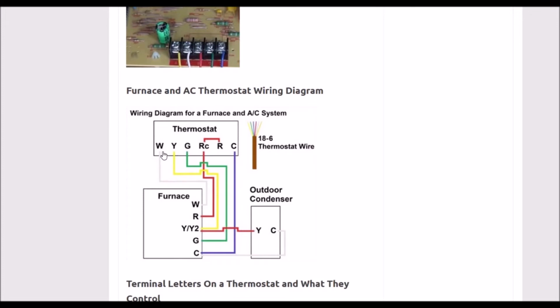And this W wire right here is going to be the call to heat to turn on the furnace. The way this works is the thermostat is just a switch. So when a certain temperature is reached, say you have the thermostat set to turn on heat at 72, as soon as it reaches 72, it clicks the switch and it sends this R 24 volt wire from the transformer to W, which will then kick on the furnace. This Y right here is a call to cooling, so that would turn on the air conditioning. And G is for fan, so that would turn on the fan. For a furnace, you really wouldn't be worried about the Y or G. You'd just be worried about the W, and that it's getting 24 volts when the thermostat kicks on.